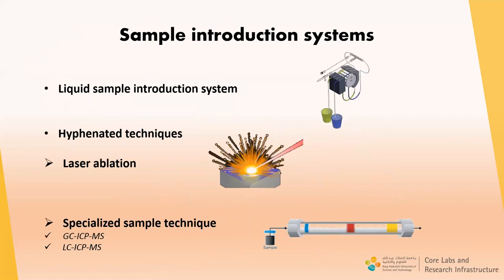The first part of the ICP-MS spectrometer is the sample introduction system. There are different ways a sample can be transported into the plasma; a liquid sample introduction system is used most often. There is also the so-called hyphenated technique, where two analytical instruments are coupled and one is used as a sample introduction system. ICP-MS spectrometers coupled with laser ablation are very popular and widely used for direct determination of major and trace element concentrations and isotopic ratios in solid samples. For speciation analysis, chromatographic instruments are used as the sample introduction system, with chromatographic columns separating analytes and transporting them into the plasma at different times.